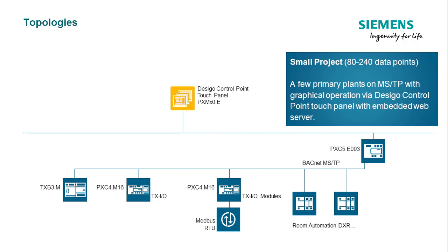If a BACnet MSTP network is preferred, the MSTP variants of the primary automation stations can be used with the system controller PXC5 for the integration. The IOs can be extended using the TXIO modules, and Modbus RTU integration is also supported.